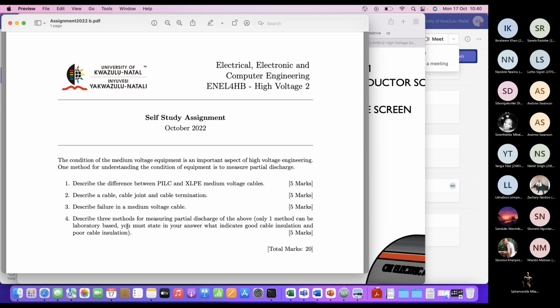Cable termination. So this is where the cable can come up and join a transformer or a piece of switchgear, etc. It's very important that that's also got the correct insulation. Remember, you're taking high voltage, you can't just put it out. You actually need a specific type of termination to control the electric field, to protect it from the elements, to protect the cable internally, to make sure that the oil is not going to leak. So there's a lot more to it than you actually think.